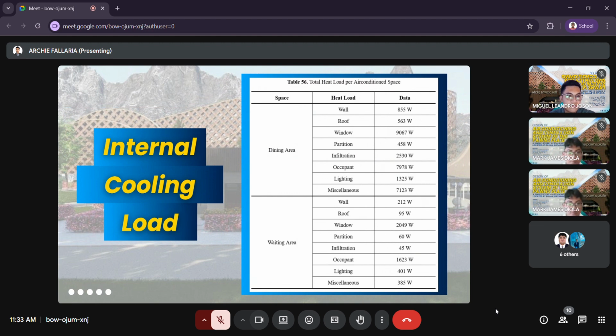Now for the total heat load per air-conditioned space. This table presents the total heat load calculated for each conditioned space within the building. This data reflects the combined effects of internal and external heat gains, including conduction and solar heat through walls, roofs, windows, and partitions, infiltration of outside air, and heat generated by occupants, lighting fixtures, and miscellaneous equipment. Understanding the distribution of these heat loads is essential for designing efficient HVAC systems and ensuring optimal comfort conditions in each space.